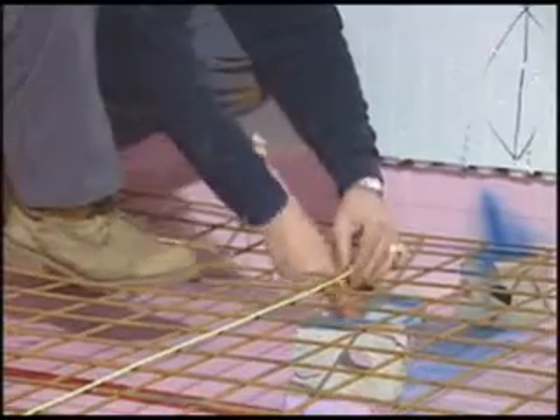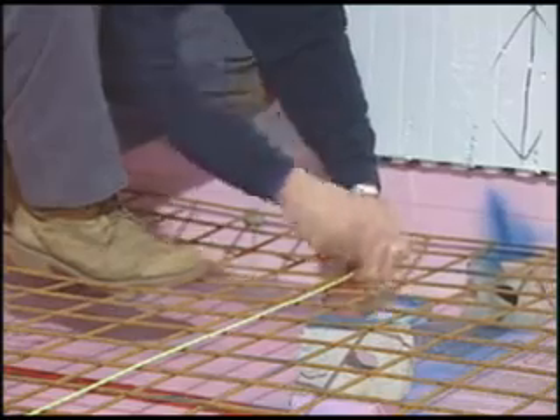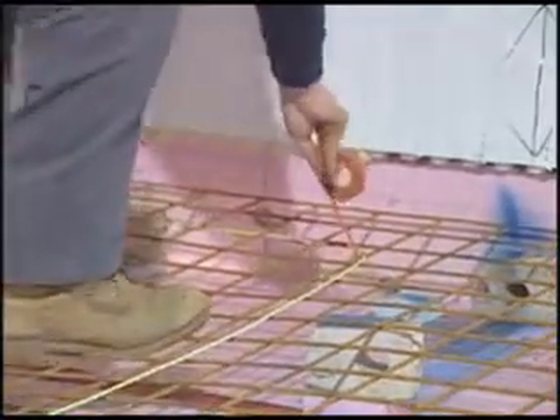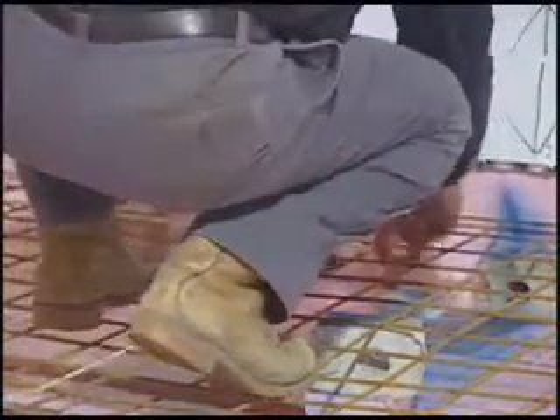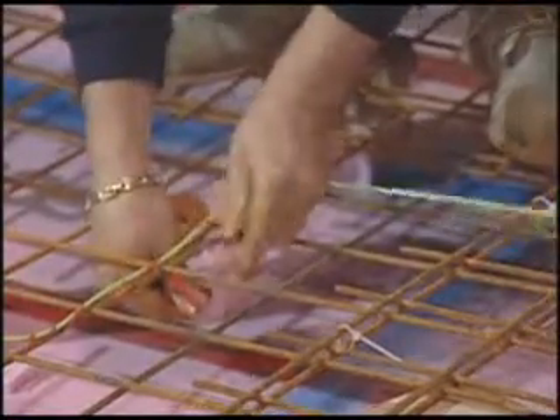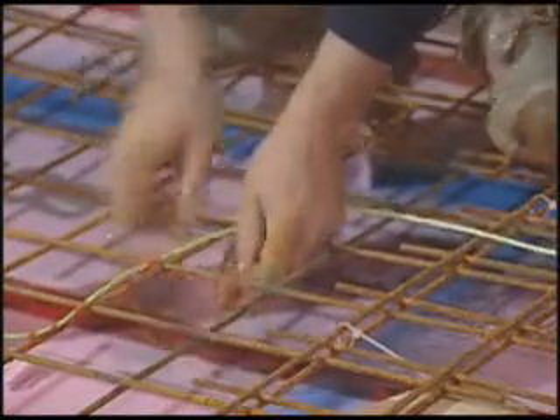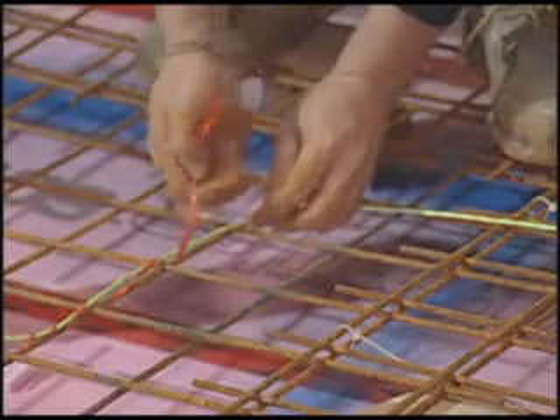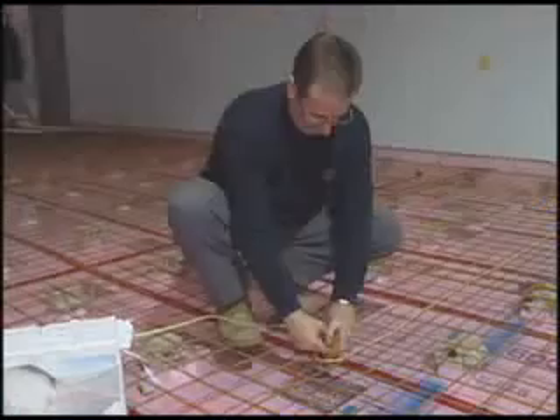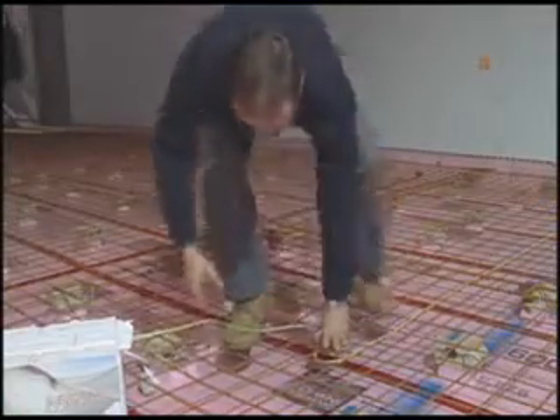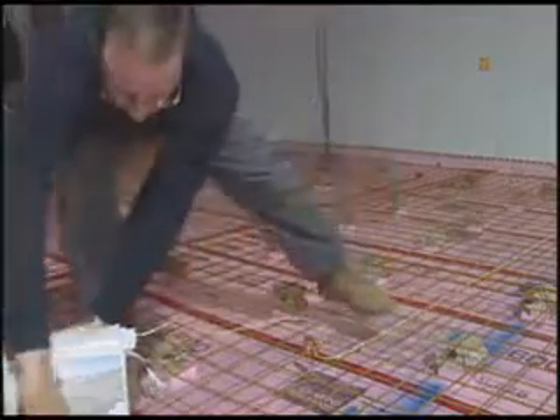Unwind the cable and attach it in a uniform manner to the mesh with Flextherm adhesive tape. This is done by winding the tape around the cable and the mesh in a spiral pattern. Apply a slight tension to the cable and make sure that it is uniformly secured along the entire length by using one turn of tape for each square of mesh. Take care that you always observe the pre-established spacing.